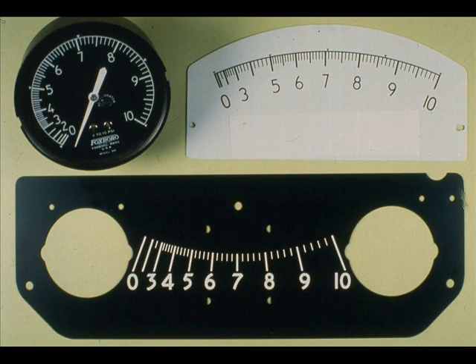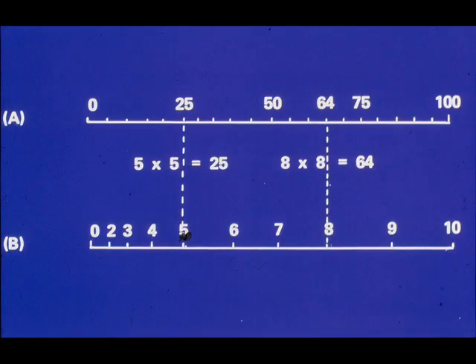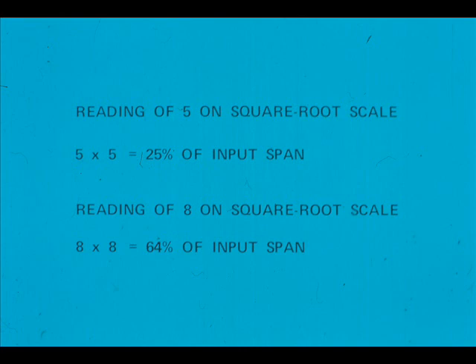When calibrating flow transmitters, it is often necessary to work with square root scales. One must calculate the percent of input span represented by a given reading on the square root scale. Scale A represents a 0 to 100 linear scale, and Scale B is a 0 to 10 square root scale. Notice that when a number on the square root scale is squared, it equals the number on the direct scale immediately above. To convert a reading on a square root chart to percent of span input, it is only necessary to square the reading and add percent.